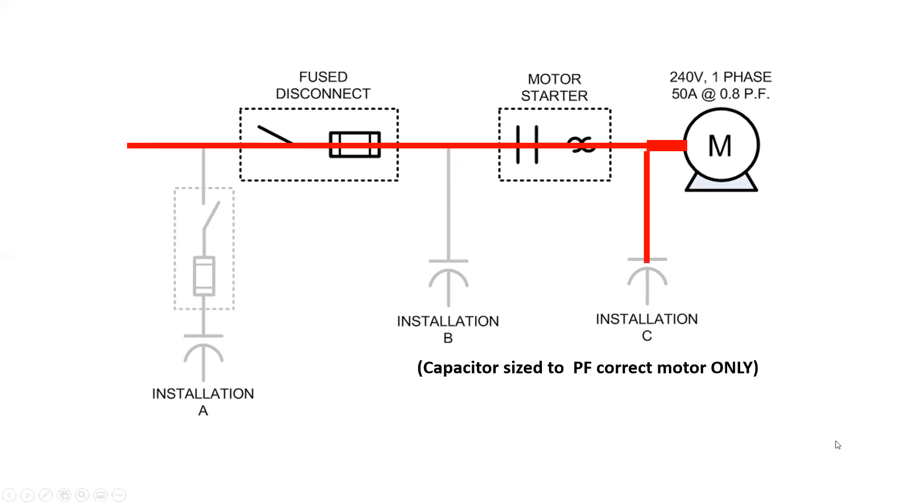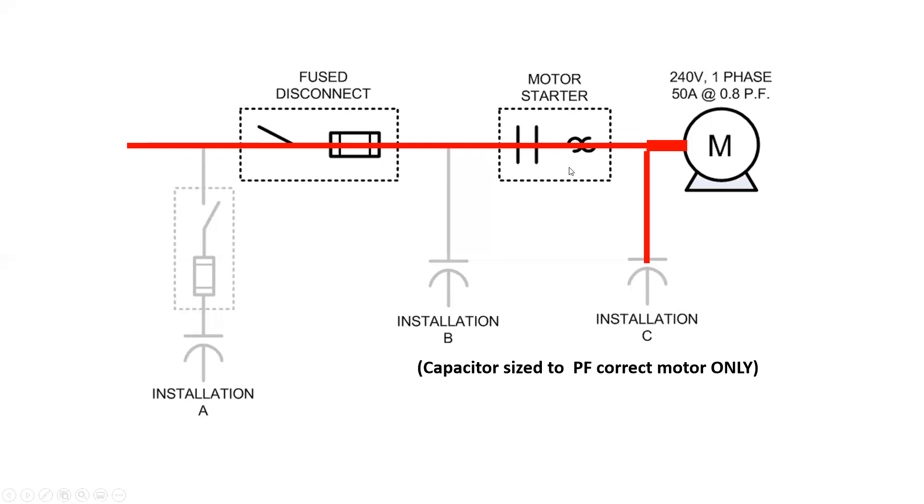And finally, we have this one here. We installed the capacitor to power factor correct the motor only. And again, now we need to start considering what about all of the overloads here? What size are they going to have to be? It's going to be a smaller value of current. And because of that, this may have to be sized smaller, or at least the overloads need to be sized smaller in order to properly protect the motor.